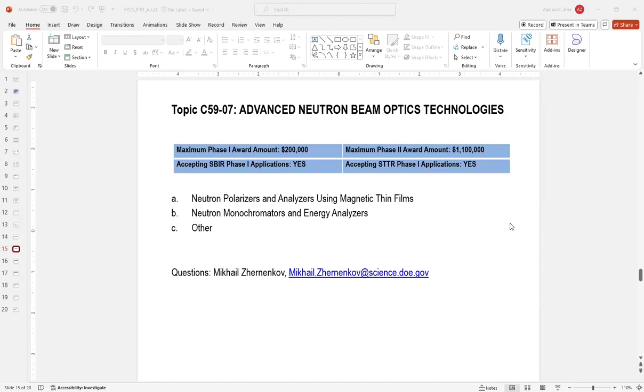Both of these require a defined crystal mosaic to meet instrument resolution requirements, and this is where the key innovation lies. Being able to define, quantify, and deliver consistent monochromator crystal performance across a range of sizes and crystal materials is critical to success for proposals that target this subtopic. Performance should meet or exceed those stated in the key requirements of the subtopic, and utilize a measurement of crystal mosaic to show achievement of those requirements where applicable.